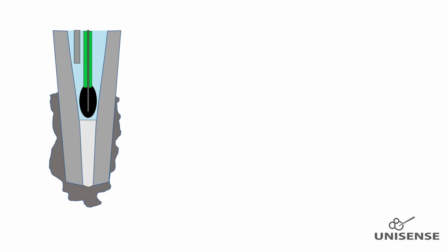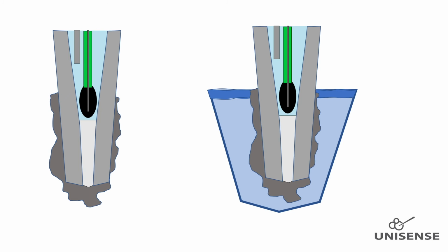If the sensor tip gets biofouled or covered with sticky polymers, it might measure incorrectly. The sensor tip tolerates almost all possible cleaning substances like alcohols, acids, detergents, proteinaceous solution, etc. So it is recommended to insert the sensor in different cleaning solutions to see if this solves the problem, as the first attempt to remove the fouling.